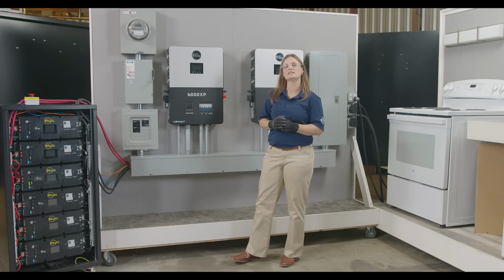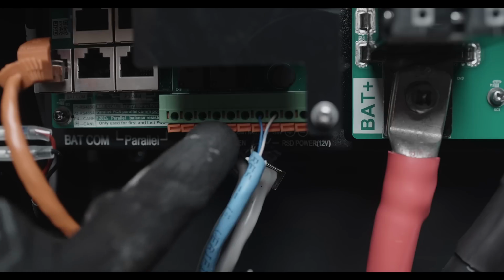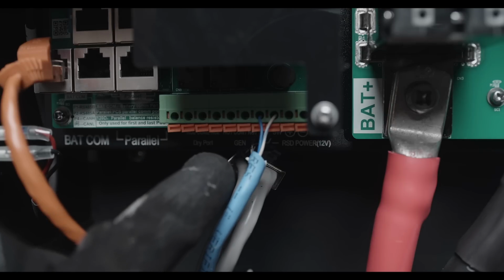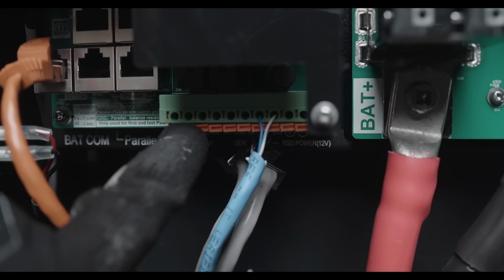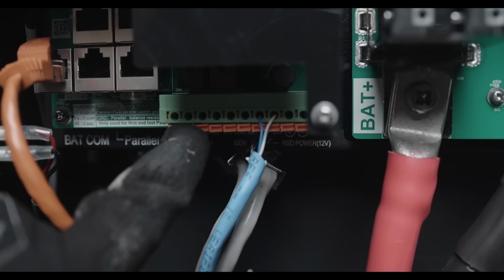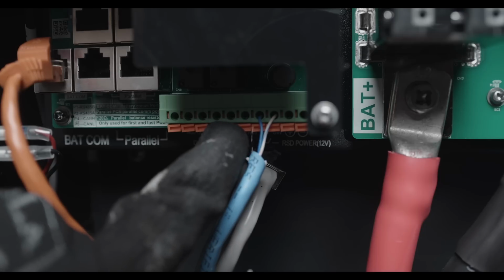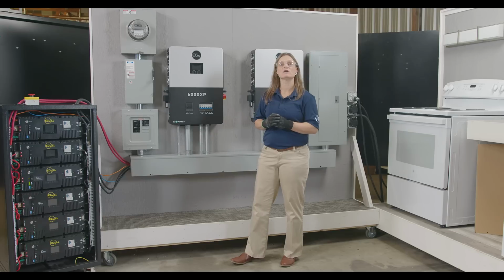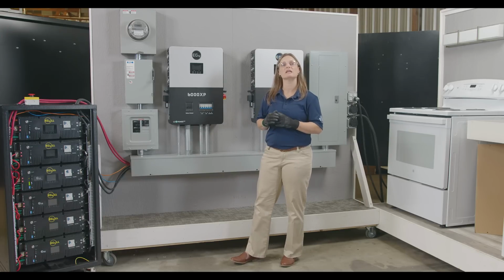The EG4 6000XP inverter features 2 dry ports for enhanced remote control capabilities. The normally open 2 COM2 port can activate external devices when your battery voltage reaches a preset warning level, while the normally open 1 COM1 generator port allows for automatic generator startup. In the event of a grid outage, this inverter can seamlessly integrate with a generator. Ideally, one that's at least 1.5 times the inverter's output and has less than 3% total harmonic distortion.